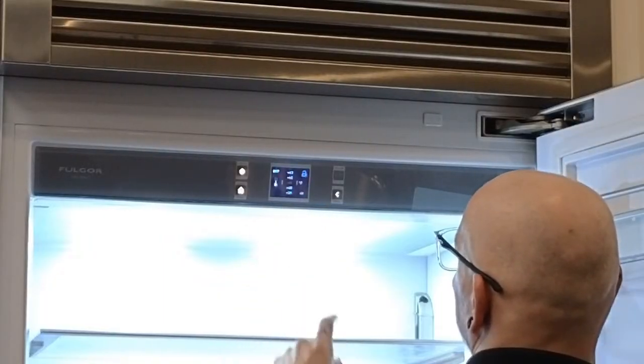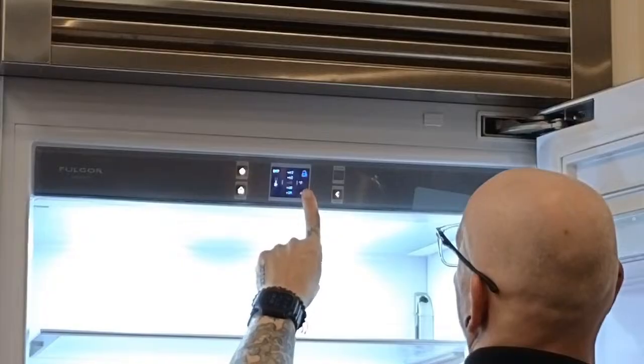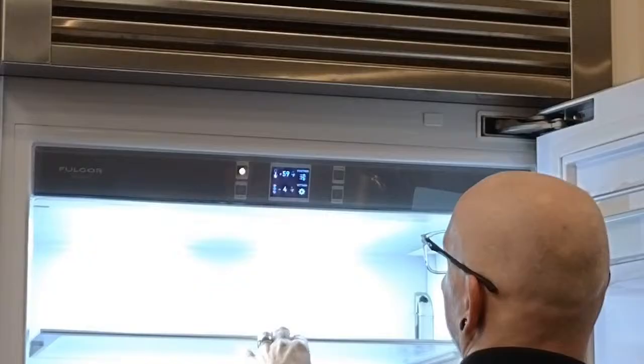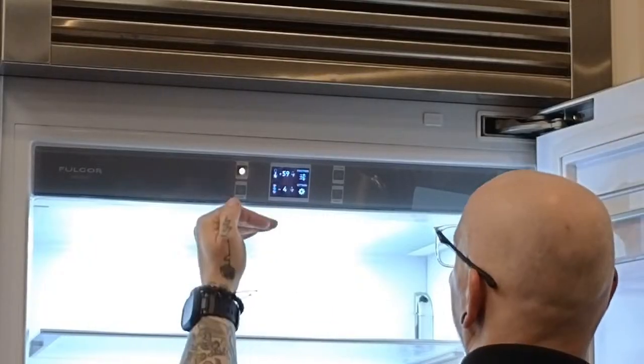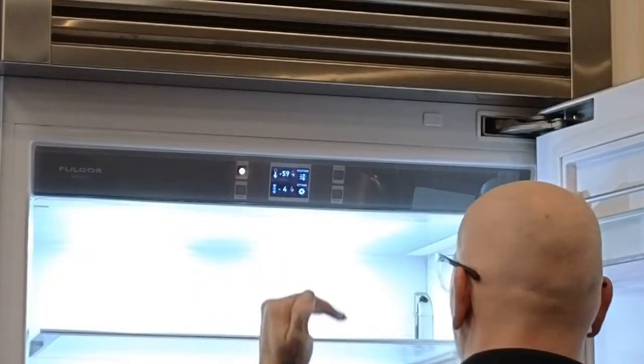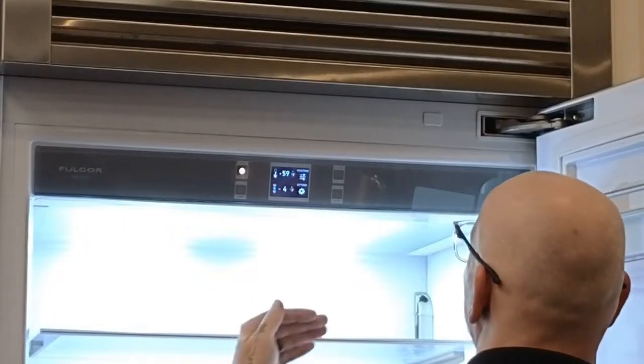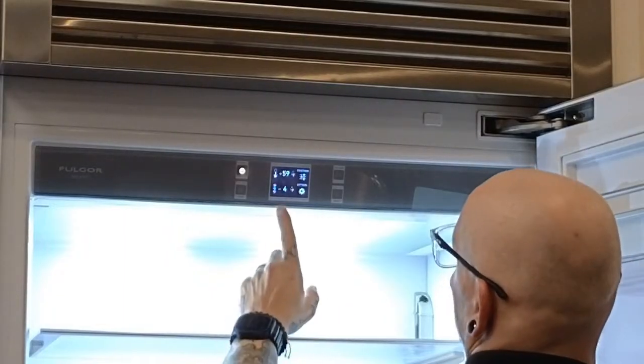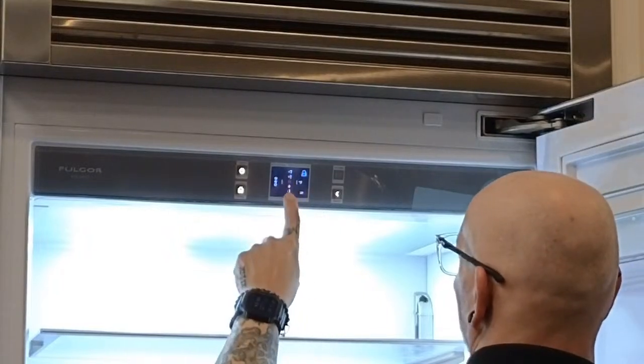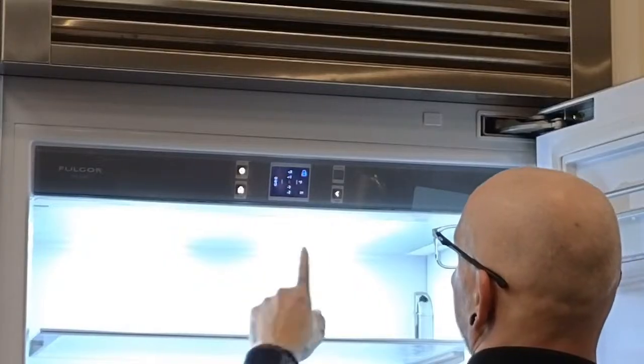So like I said, you can change temperatures. This fresh food section, you can scroll up or down. They come preset from the factory at 41 degrees. We've had the door open for some time, so we're up at 59 degrees right now. It's a rolling average. So when the customer does change that temperature and then hits OK, it's not going to automatically display that temperature. It's going to show the rolling average. Once it hits that temperature, it'll maintain that temperature. Same thing for the freezer. Push the freezer temperature, and you can scroll and adjust your temperatures there. Freezer comes preset at 0.